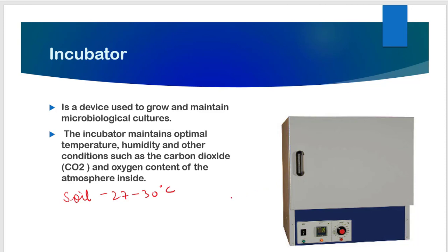The incubator allows precise temperature control rather than relying on room temperature. If the room temperature is 10 degrees Celsius, an organism may not grow or will take more days to grow at that temperature. Every organism has a certain temperature requirement to grow. For instance, if a microorganism isolated from the human body likes to grow at 37 degrees Celsius, we change the temperature settings of the incubator accordingly.